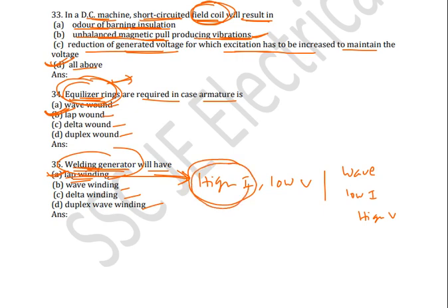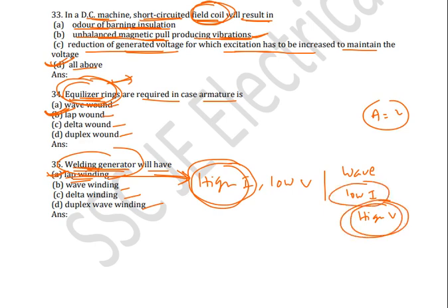In wave winding, only two parallel paths exist — number of parallel paths equals two. That is why wave winding is used for more voltage and low current applications. In a welding generator, we use lap winding for getting higher current.